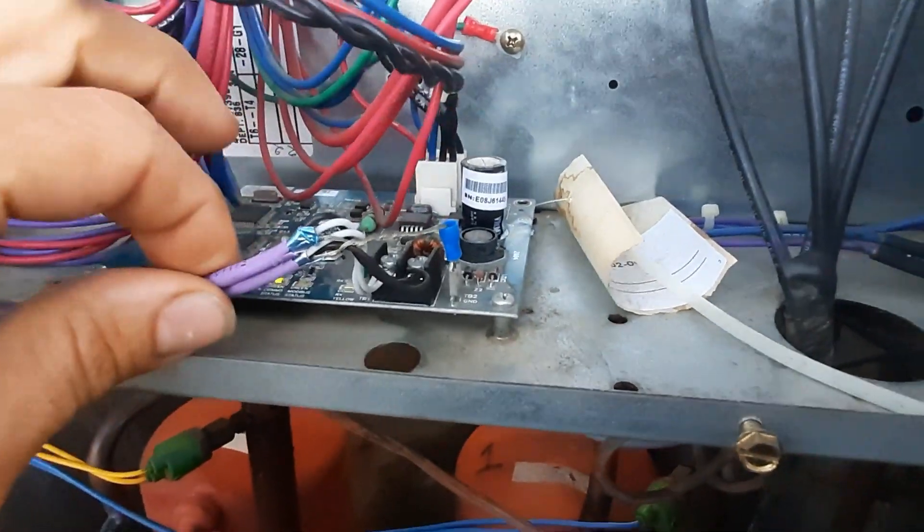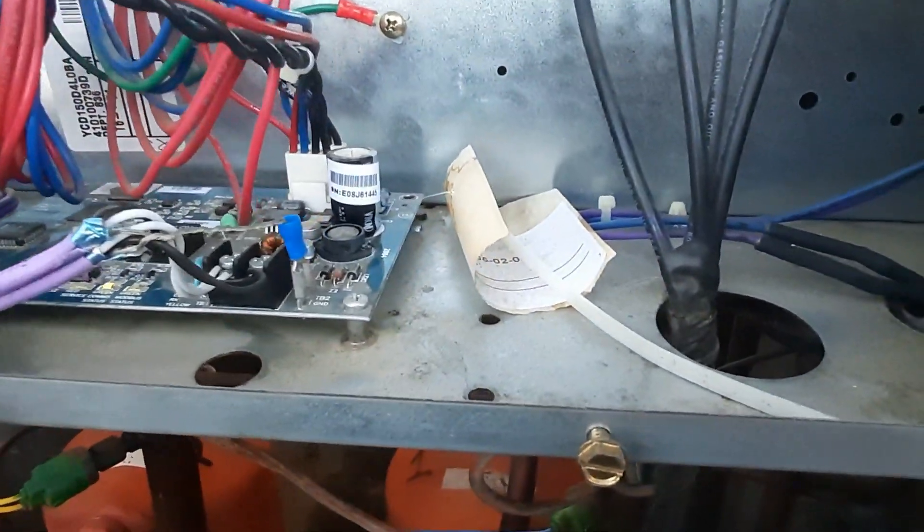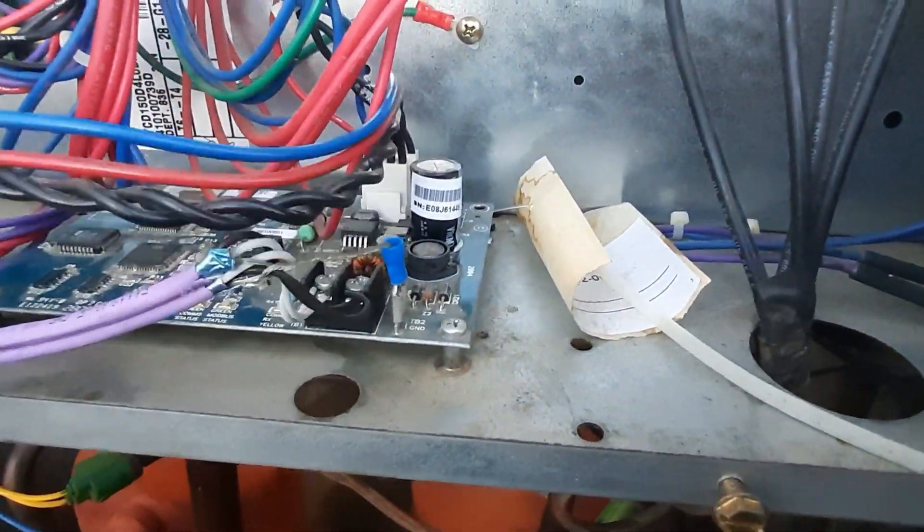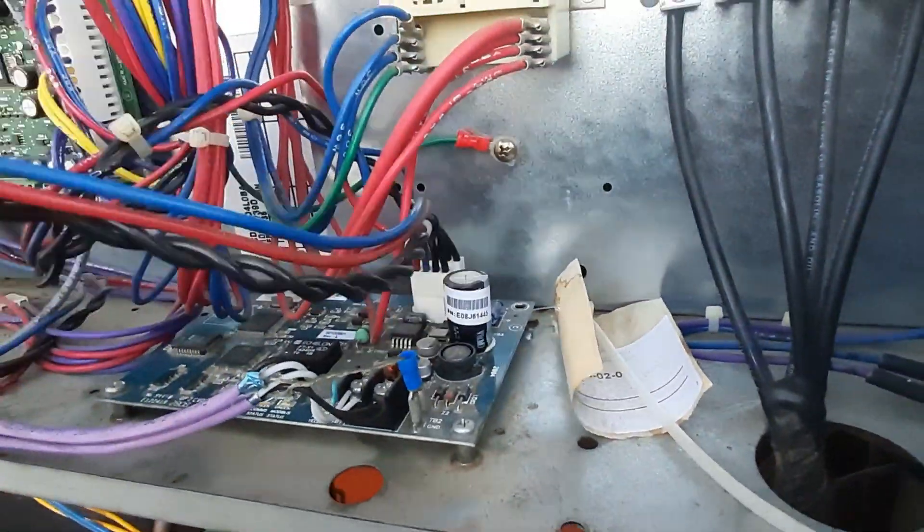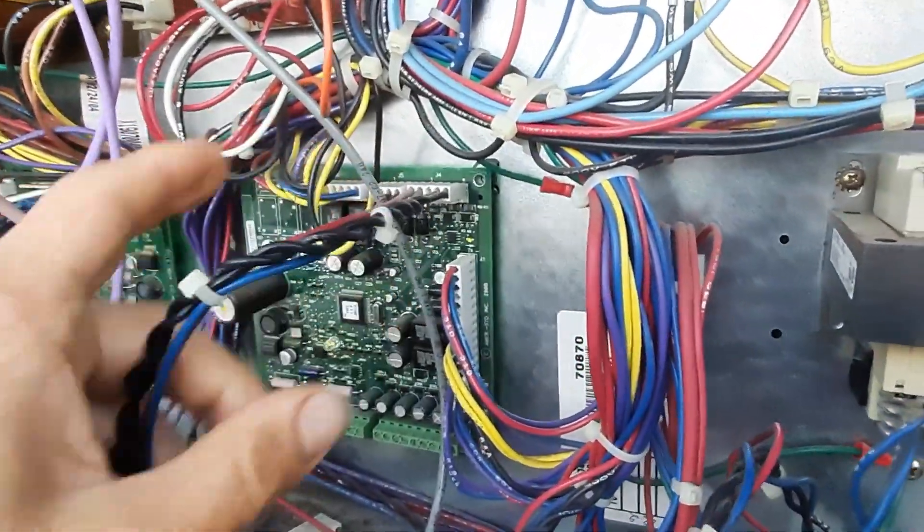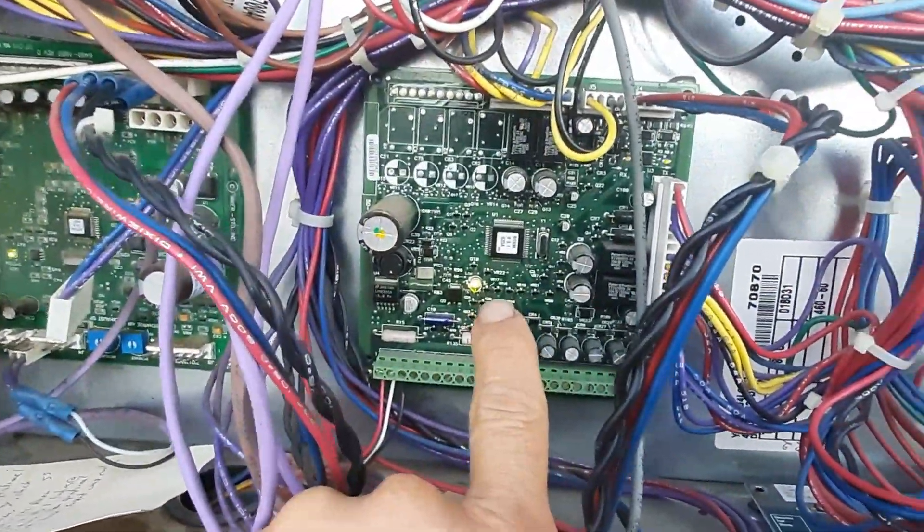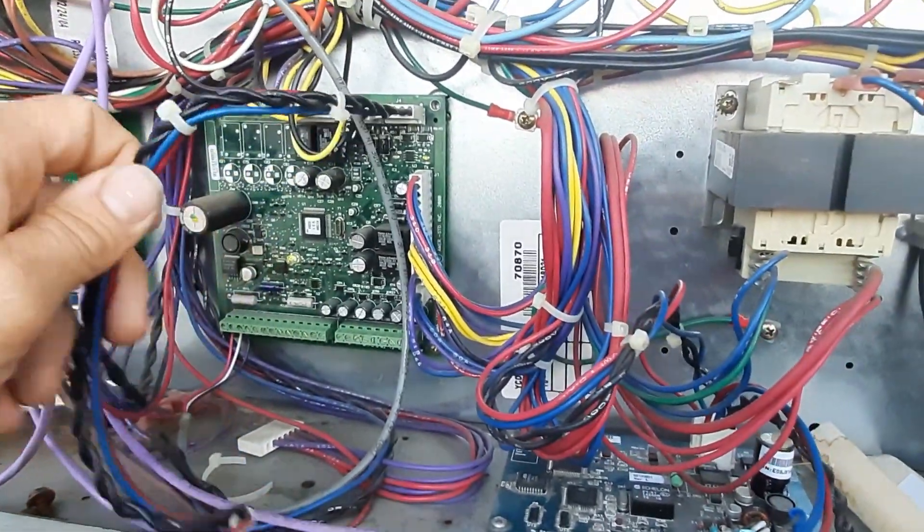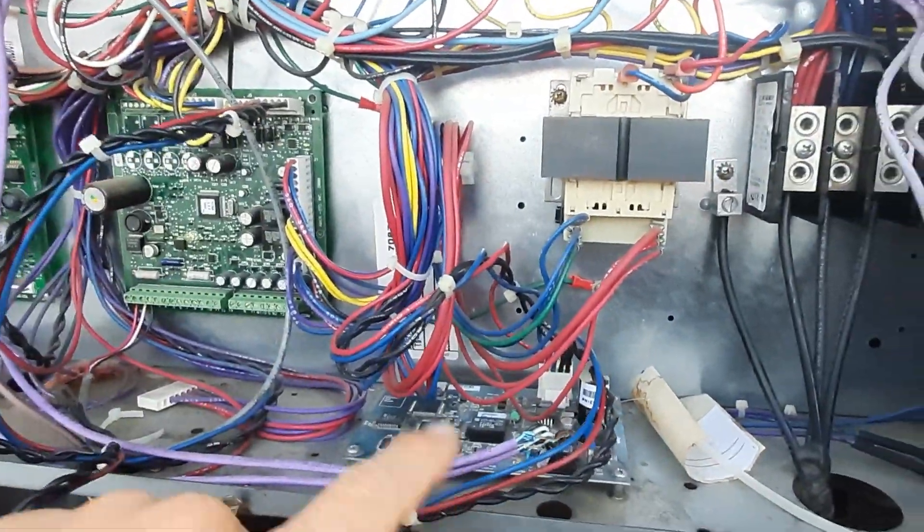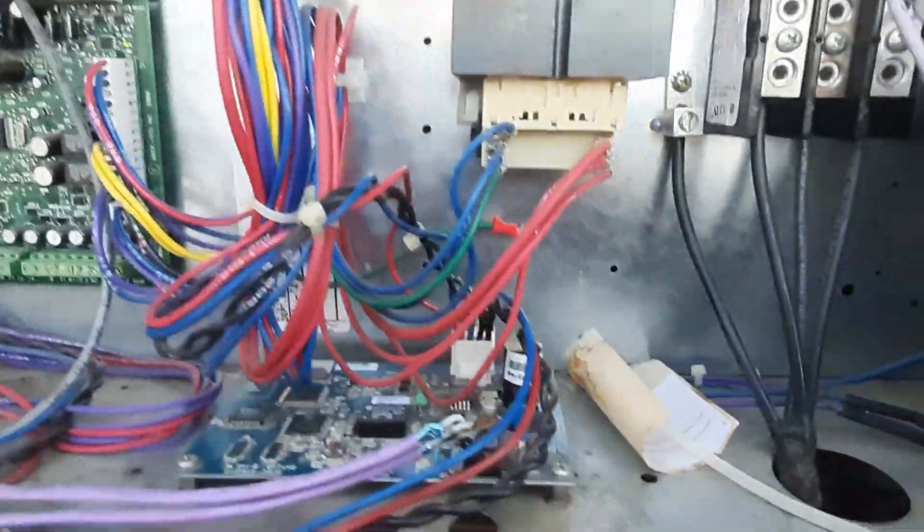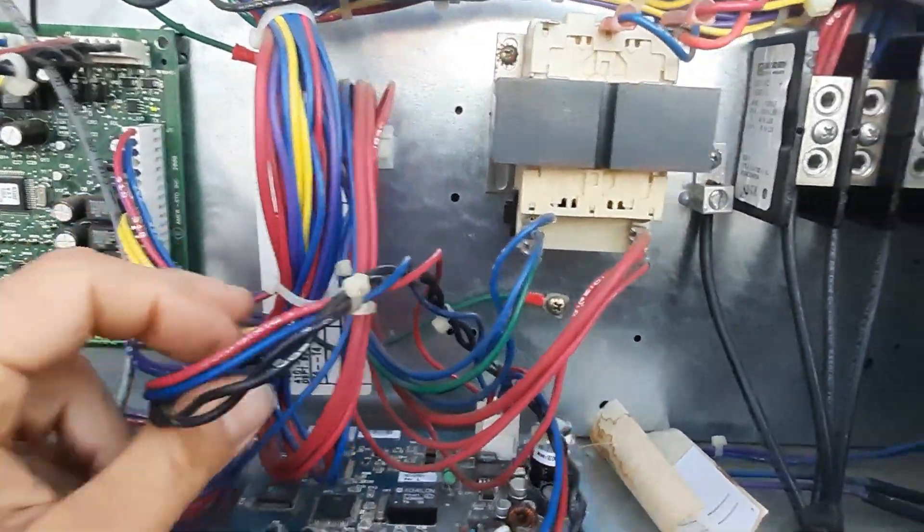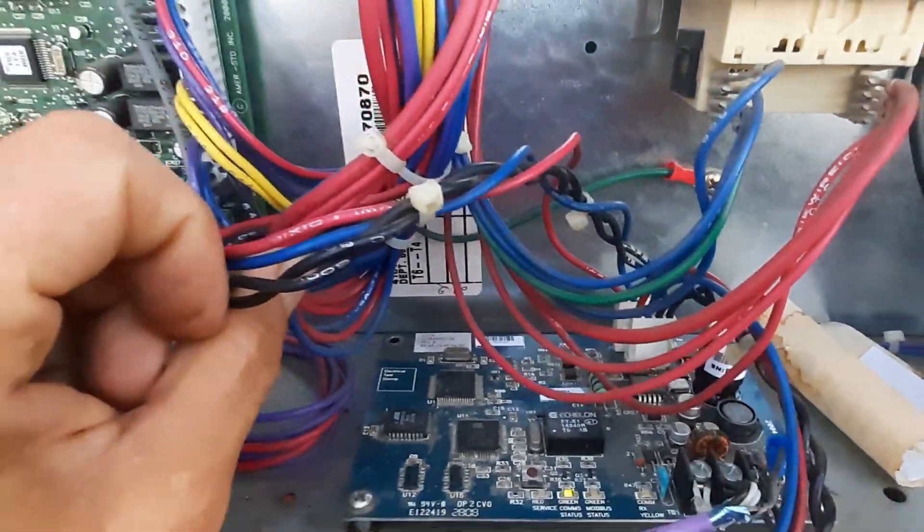But the two aren't talking one way or another, so we're gonna start with the LCI, see if that brings it back up. We'll bring our neuron ID back down and cover that up, make sure we get the right number on there. Let's go over and see what we got. So what I'm saying about the communication, this is my comm link here. This communicates all the information the LCI has down to that control panel. You can see this wire harness is actually plugged into the RTRM board. So this RTRM board does the same thing it does in every other Trane unit, it does all the controls. This just relays the message back to the LCI to tell the system what it's doing, and we're not getting that for some reason.